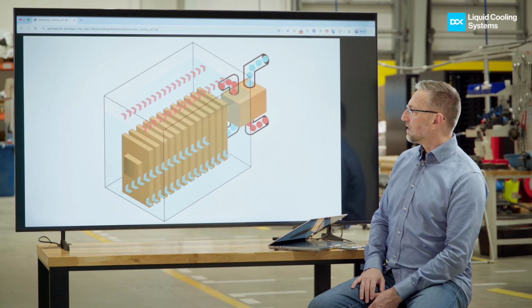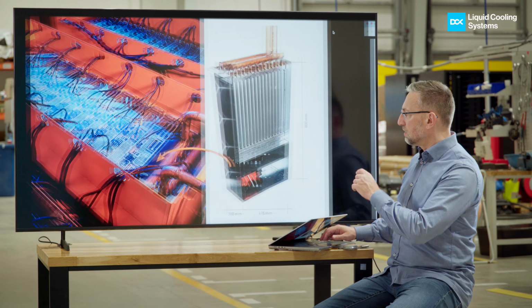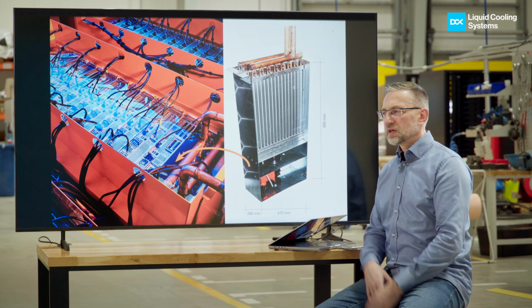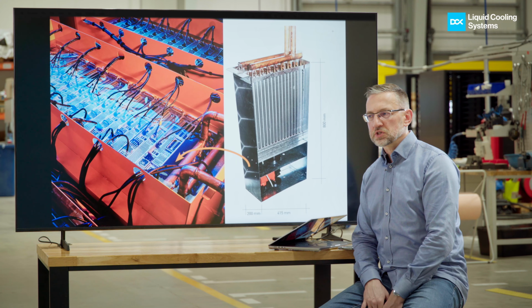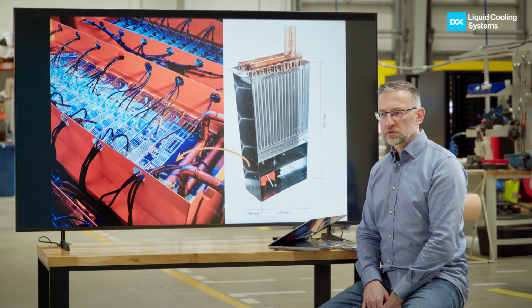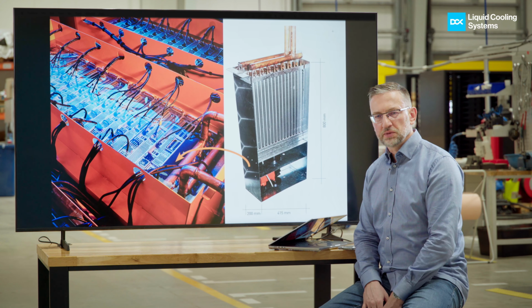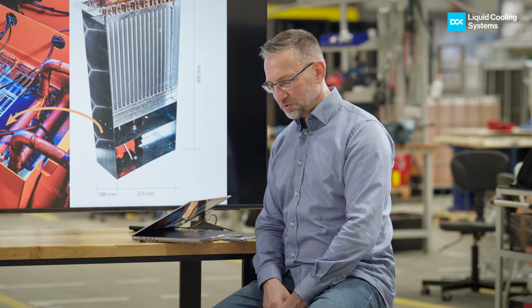And there's a startup from Europe which took that idea. They packaged it, but it's not the best solution, honestly. So we don't need CDUs. We only need heat exchangers and pumps which circulate the fluid internally within the tank and then exchange the heat to the outside water-based cooling loop, which delivers that 40 degree warm water to the tank. So yes, we don't need CDUs for immersion cooling.